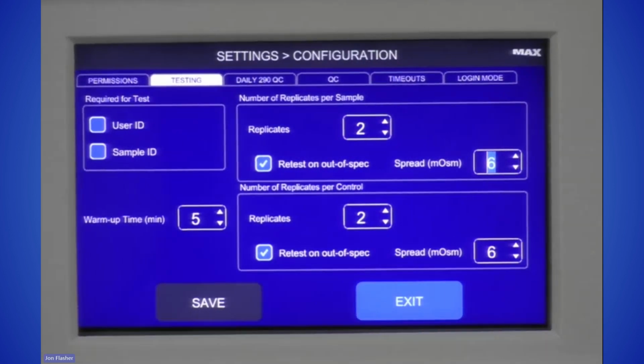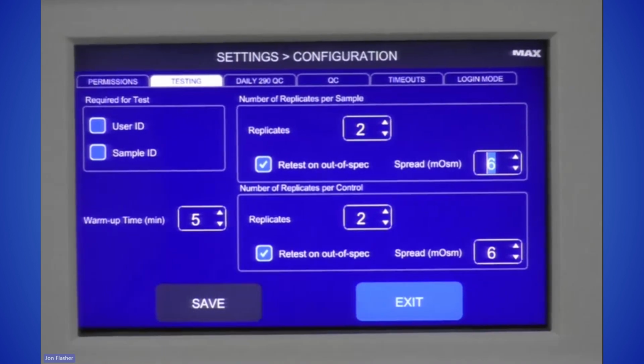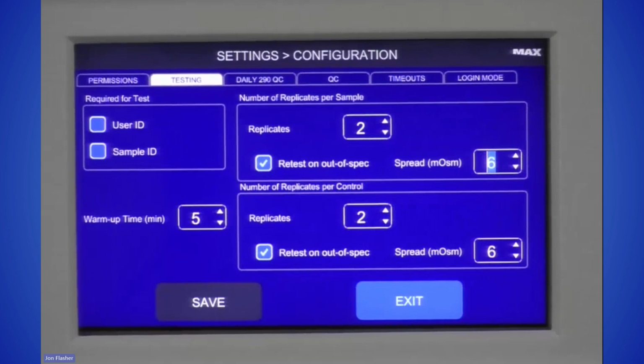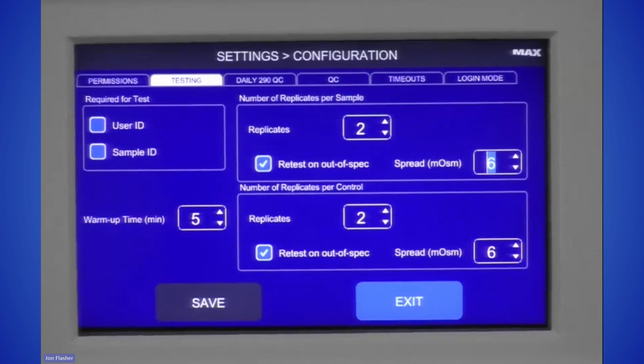So what does that mean? You can check things like a user ID or a sample ID to be required for testing on the instrument in general. Or over here on the right of the screen, you can pre-program replicates. Some laboratories, based on the voice of the customer information that we collected from labs on what they want in this software for the next generation osmometer, prefer to run osmolality testing in duplicate for each sample. So this software feature gives laboratories the flexibility to pre-program duplicate testing for each sample. If you wanted to run 2 tests for every sample, you can pre-program that here.